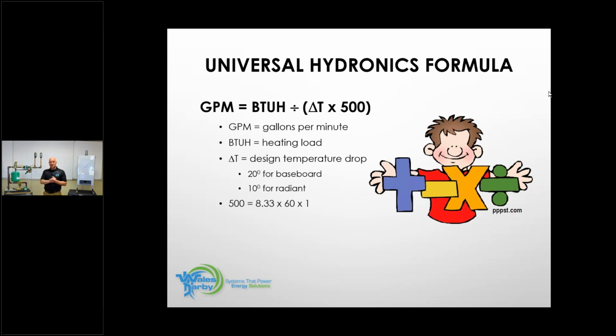So basically what that formula just told us is, if I know the BTU of this boiler and I know the delta T times 500, I can figure out what the flow rate needs to be to support this boiler and the piping. We'll go through the piping diameter in a little bit. That is one way to utilize that formula. The other way is, if I know 2 of the 3 in that universal hydronic formula, I can figure the other one out. It's either going to be multiply or divide. We just did the divide. We took the delta T times 500, divided it into the boiler size, and it told us that we had a 10 gallon a minute flow rate.